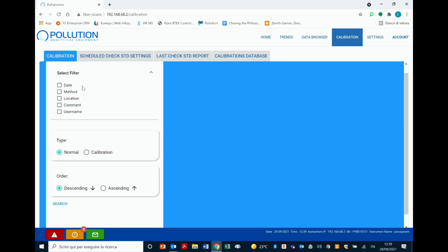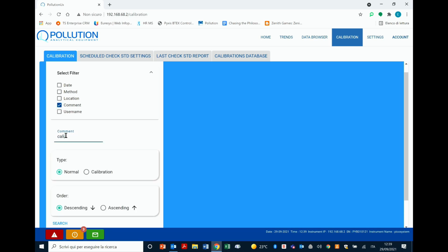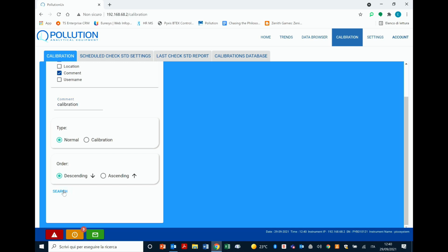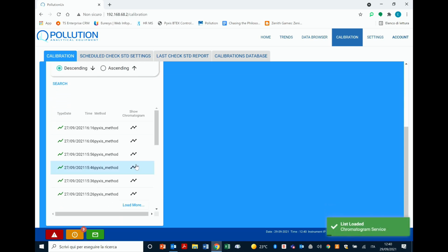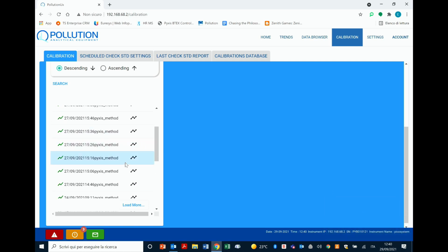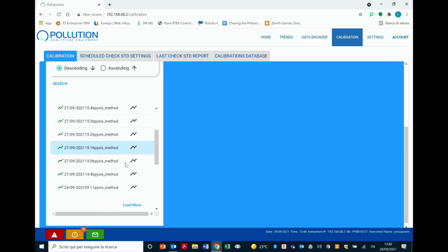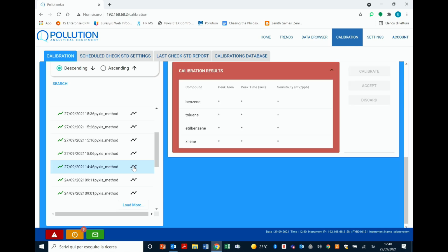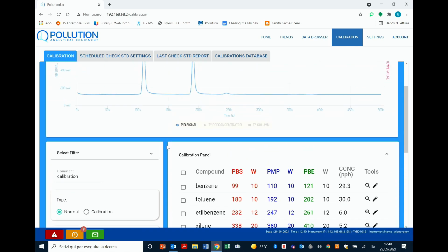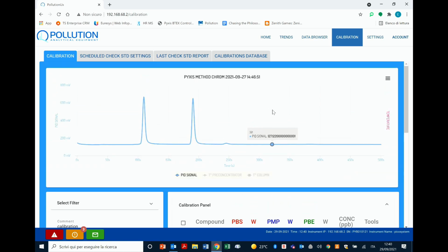Here you can filter as usual with date, method, location, comment, and will appear all the chromatograms in the desired period of time. We suggest, for example, to add a comment, let's say calibration, every time that you record a chromatogram for the calibration purposes. So we did this previously, and by pressing this and search, only the chromatograms that have been used for the calibration, so connected to a BTEX external gas tank, will appear. So you can open one of the chromatograms, the one that you need was stable enough, and this window will appear. So as usual, you can zoom in and zoom out.